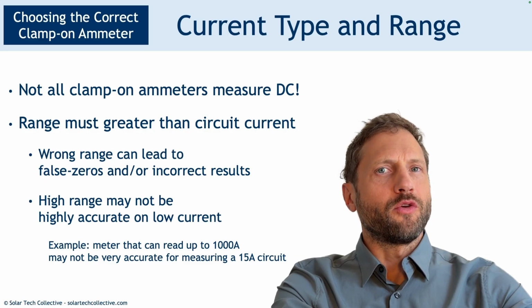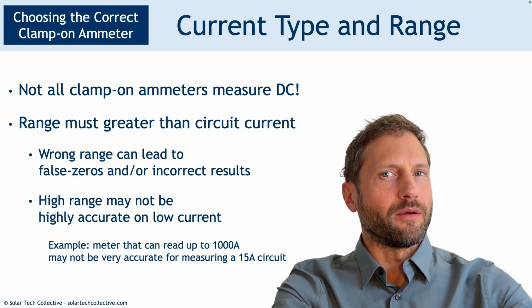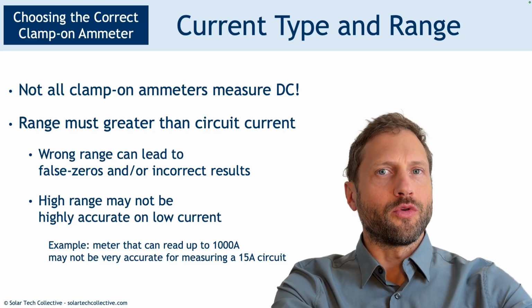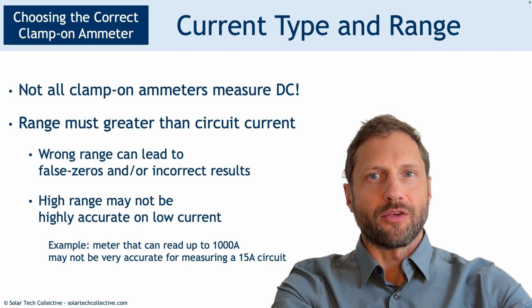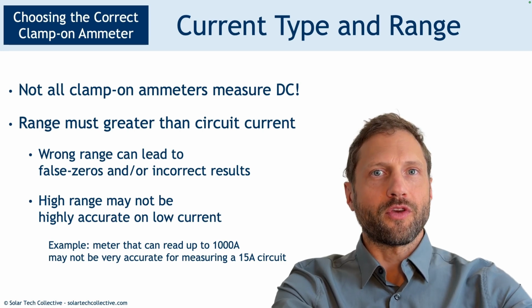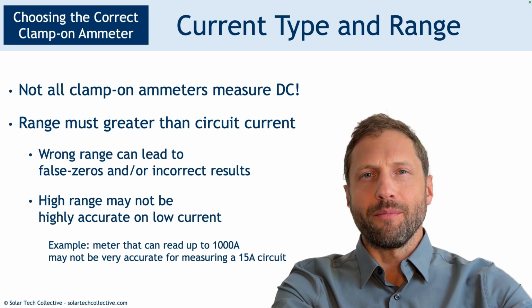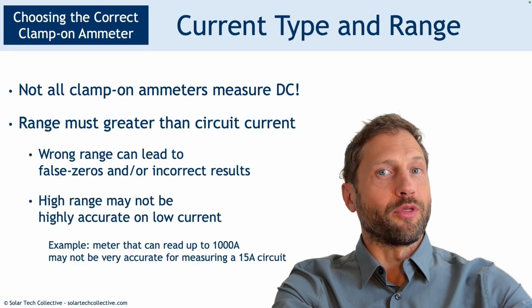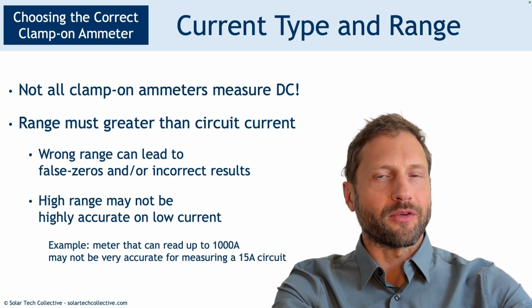So why don't we just use meters with a high range all the time? Well, if we try and use a meter with a high range on a circuit with low current, the results aren't going to be that accurate. For example, a meter with a range up to 1000 amps isn't going to be the best tool for measuring current on a 15 amp circuit.